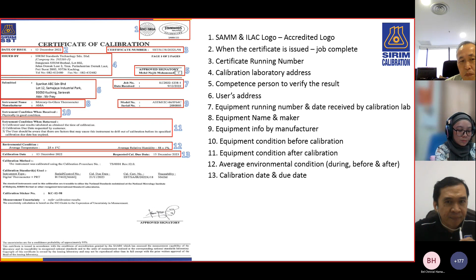Okay. And 14 is calibration method. This is the procedure that we use. Of course, we update this procedure based on changes in the circular or the industry standard. That's why it's important that we put the revision there. So at least we all know that we always follow the up-to-date circular from the international standard. And this is what we call traceability. Calibration standard used: instrument type, serial or control number, when we calibrated, and when it is due. So it is traceable to NMIM.